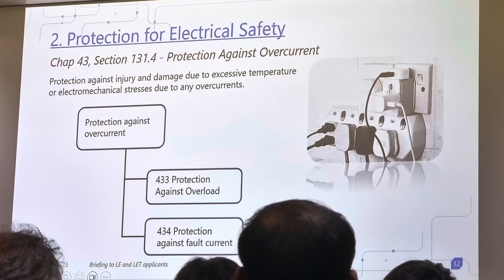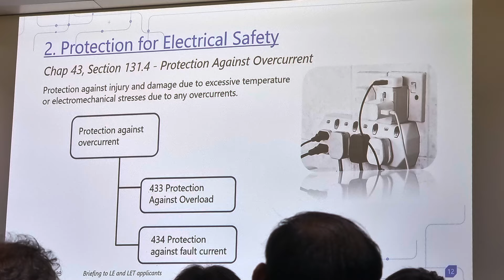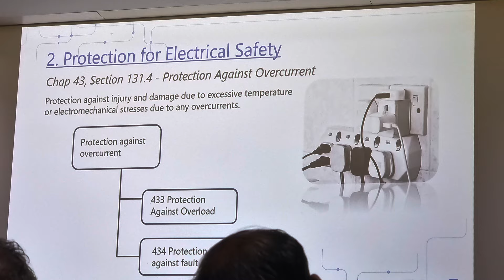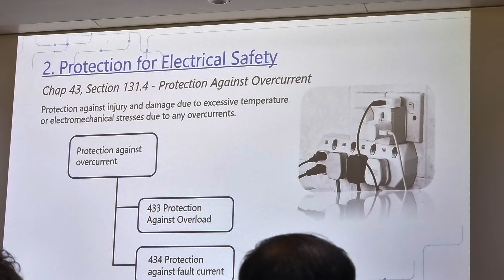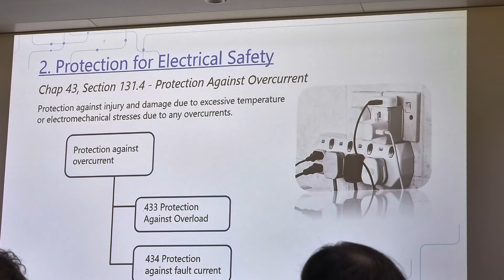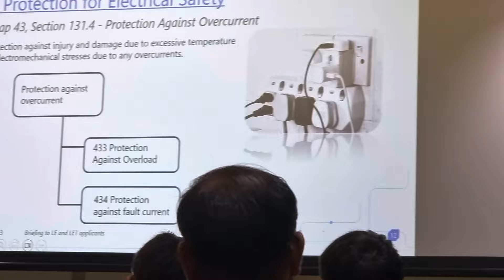The second part is protection against fault current. The fault current can be a short circuit. So this is something going wrong. That means your insulation has failed. It causes a short circuit between live conductors. So when there's a short circuit, the magnitude of the current is much higher. Overload is not that high, slightly above 100%, 120, 150%, 200%. But a short circuit can be many times, 400%, 500%, a few times more than overload. So the code does describe different ways to manage this short circuit as well as overload.